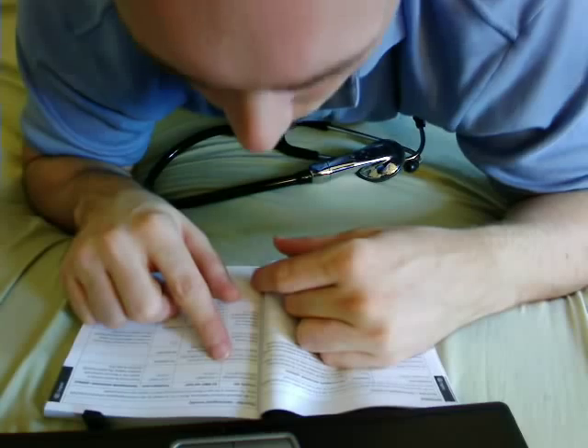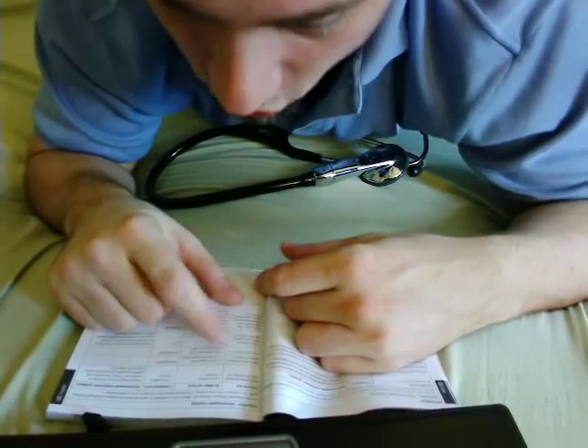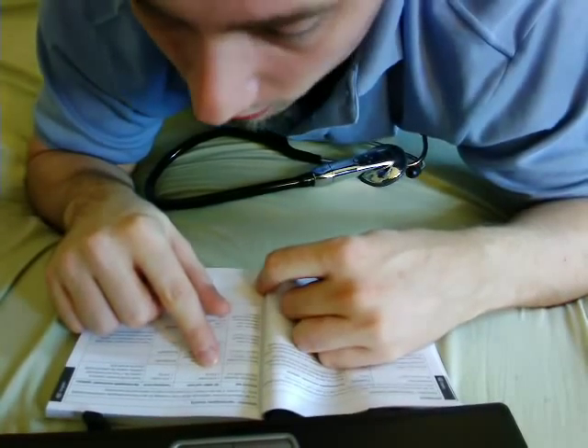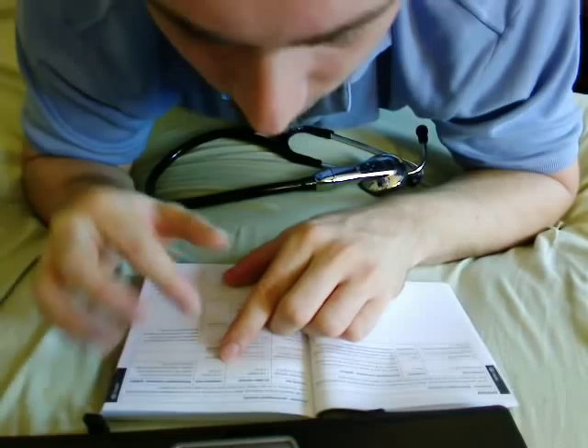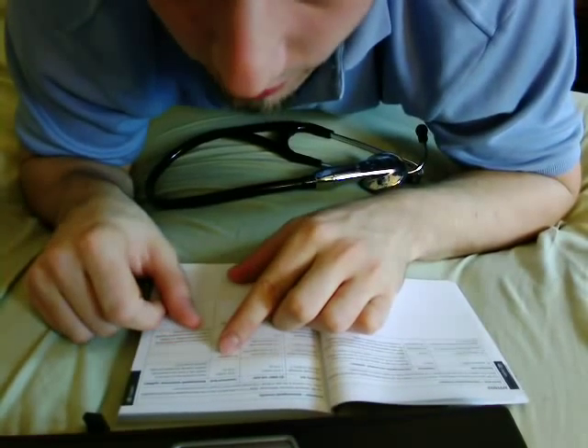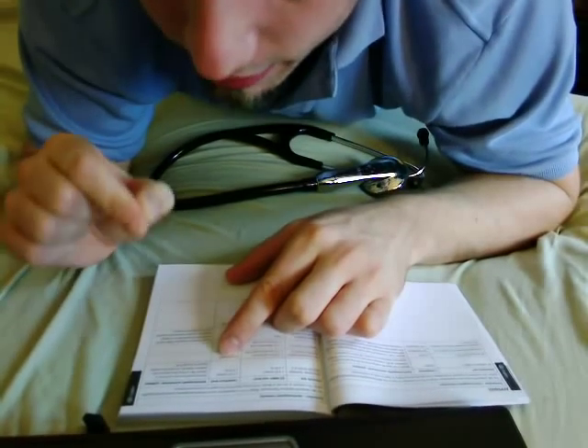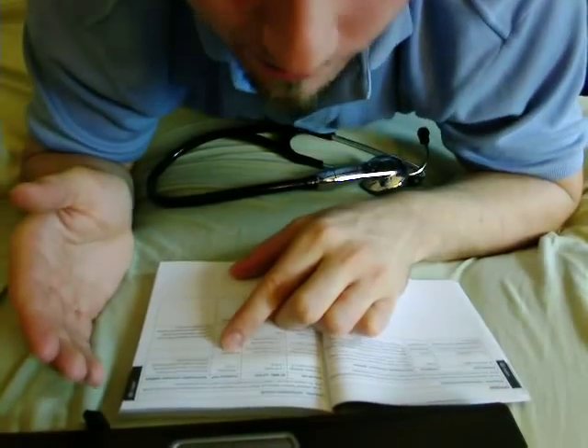Reading across the immunity tests: electrostatic discharge ESD, IEC 61000-4-2. The IEC 60601 test level was plus or minus 6 kV contact and plus or minus 8 kV air. The compliance level matches those same values. The electromagnetic environment guidance states floors should be wood, concrete, or ceramic tile. If floors are covered with a synthetic material like rubber or carpet, the relative humidity should be at least 30% — this ensures no static electricity builds up on your feet, since drier environments cause more static shock.